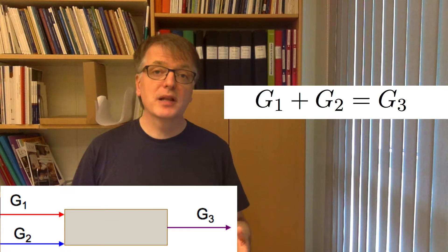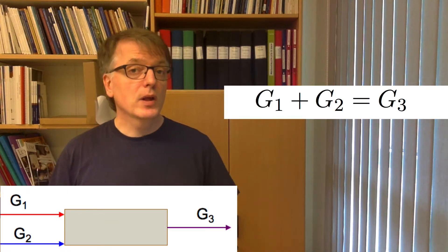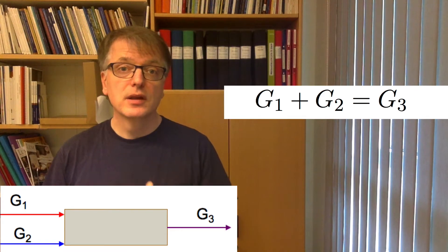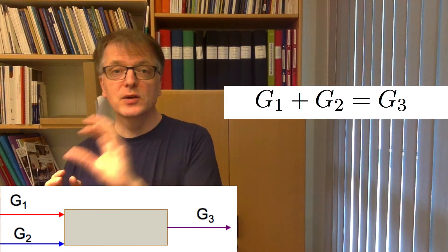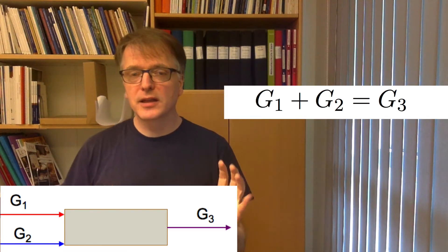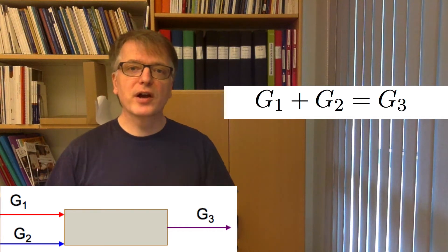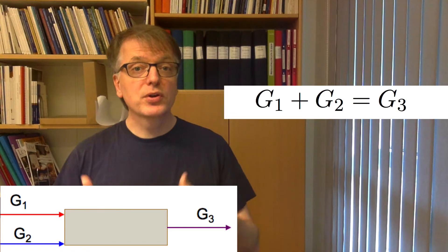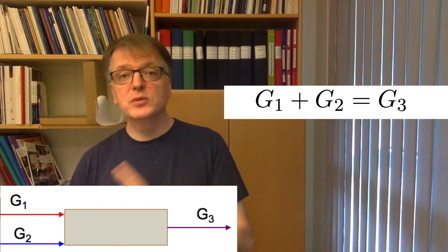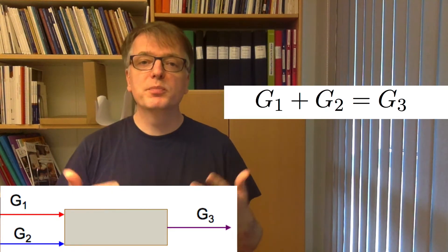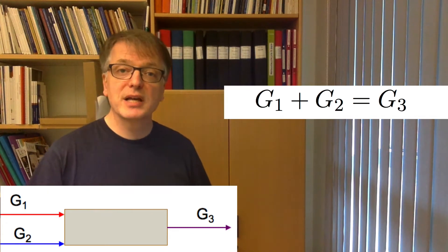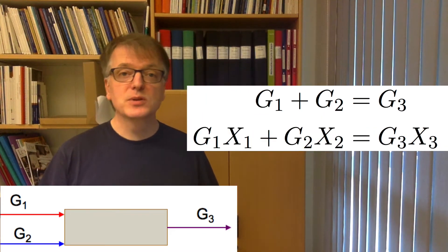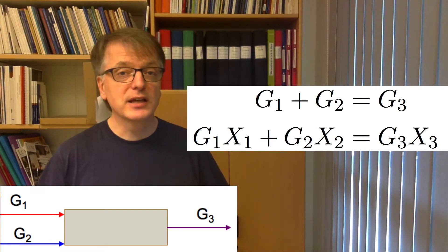What about the mass balance for water then? Well you have a water content x in each flow and if you multiply g with x what unit do you get then? Well g is in kilogram of dry air per second and x is kilogram of water per kilogram of dry air. So if you multiply g with x you get kilogram of water per second. So the mass balance becomes g1 times x1 plus g2 times x2 equals g3 times x3.